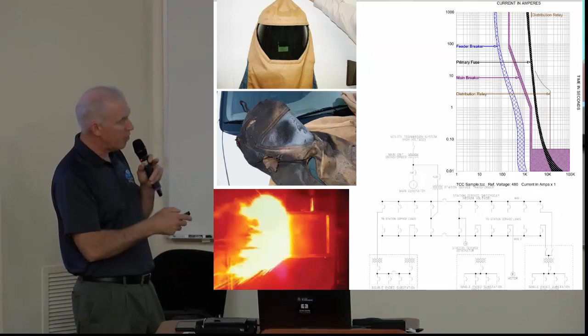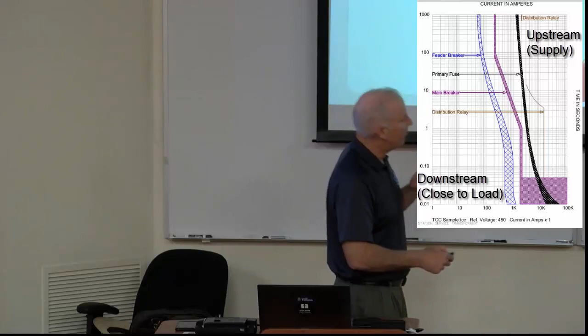What you have here is a time current curve. To the left of it means you're not going to have a breaker open, to the right it does. You see how each one of these works, this is called coordination. This is closest to the fault, or downstream, and this is upstream. Same way, this is upstream up here, and this is downstream, like this breaker, this breaker, this breaker. That's how it works.